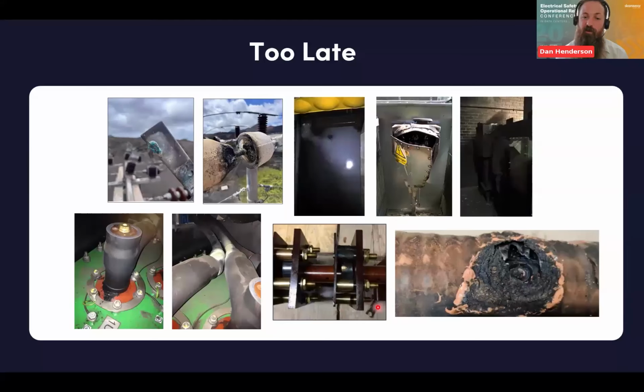And this one here is an example of where oil samples weren't getting done for DGA on transformers. They were only doing water content and acidity, wasn't picking up dissolved gases, and this transformer failed catastrophically. That's a tap changer that failed, and if they had been, they would have probably identified metal to metal thermal contact inside that transformer where it's getting arcing. So that's why it's important to do these condition-based approaches and these snapshots for the equipment health.